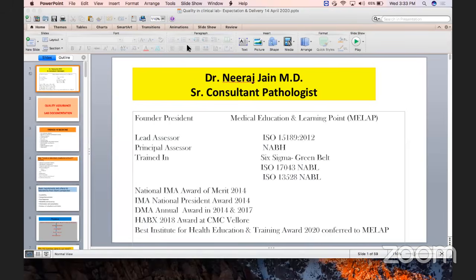But in biochemistry, various parameters go out of calibration more frequently. So you have to get that calibrated in your laboratory itself, using a calibrator. These hematology analyzers are calibrated by company people only, once in 12 months. And otherwise also, these biochemistry analyzers, hormone analyzers, etc. shall also be calibrated once in 12 months by the manufacturer.